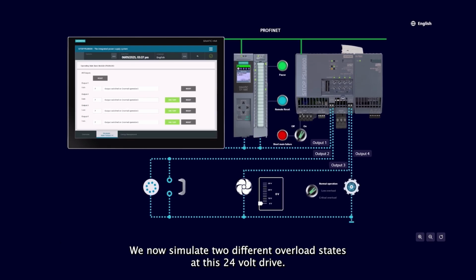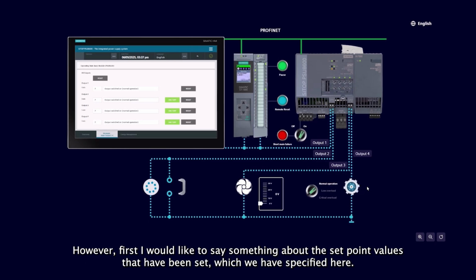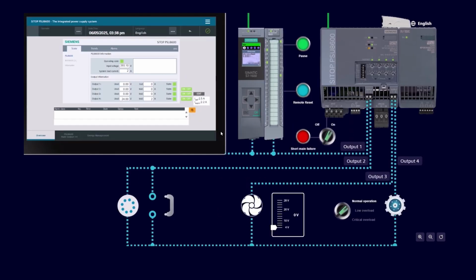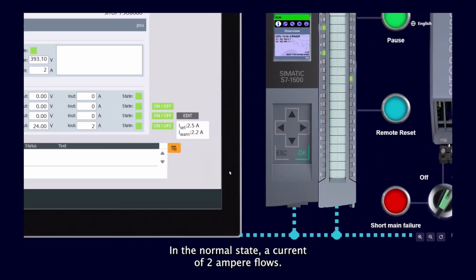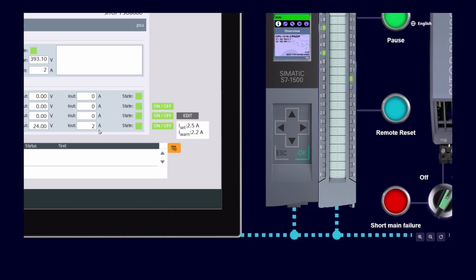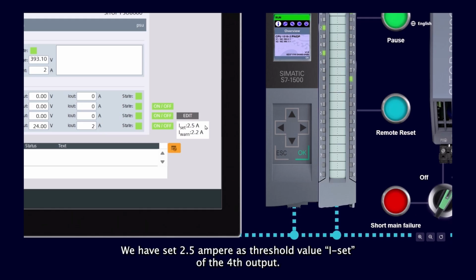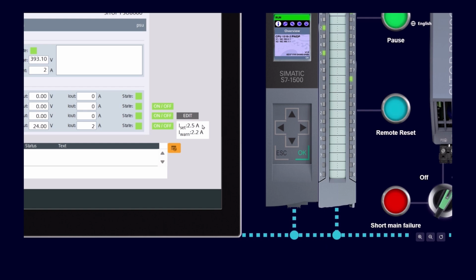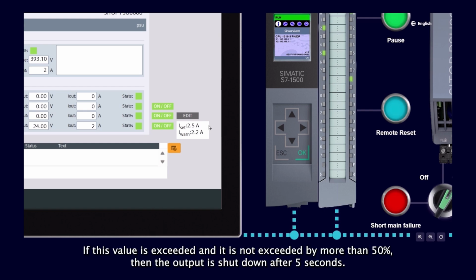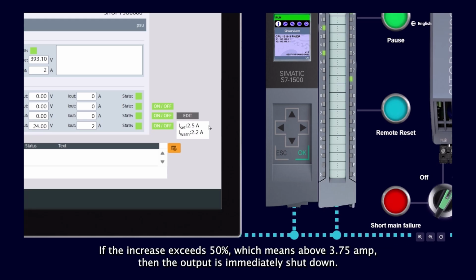We now simulate two different overload states at this 24-volt drive. However, first I would like to say something about the setpoint values that have been set, which we have specified here. In the normal state, a current of 2 ampere flows. We have set 2.5 ampere as threshold value I set of the fourth output. If this value is exceeded, and it is not exceeded by more than 50%, then the output is shut down after 5 seconds. If the increase exceeds 50%, which means above 3.75 amp, then the output is immediately shut down.